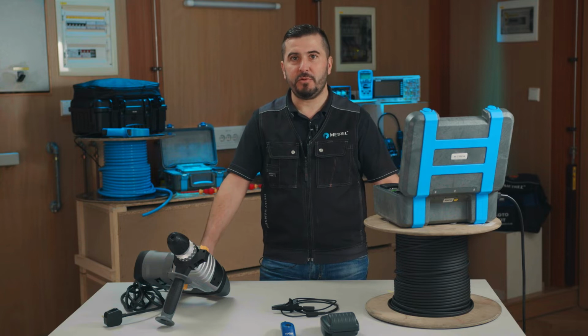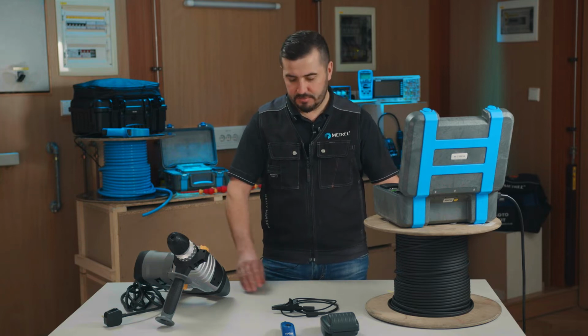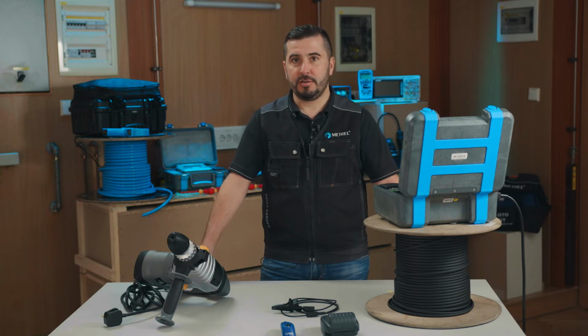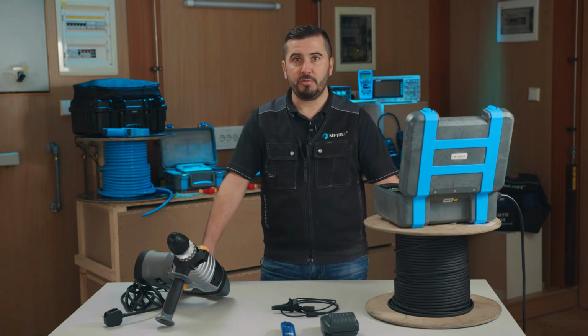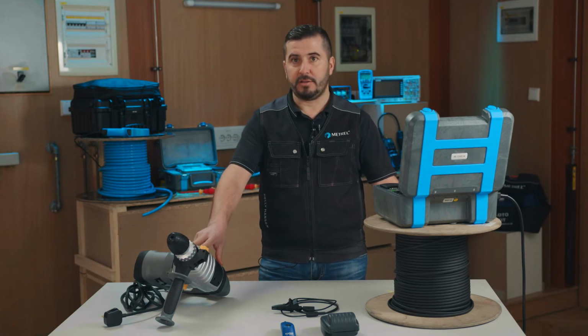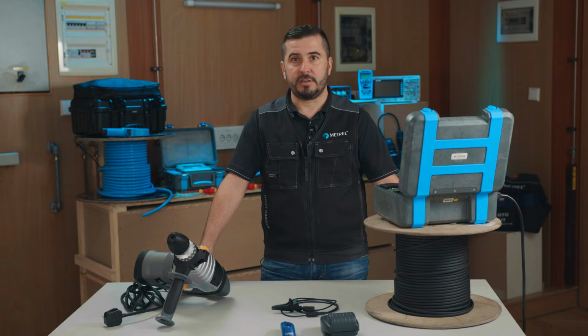So instead of it, we will perform the following tests: insulation resistance test with a probe and touch leakage test, for which the probe is also applicable. For both tests, it is crucial that they are performed with the appliance main switch in the on position. It is also important that the probe is connected to the accessible metal part. If not, then the electrical tests are invalid and the potentially problematic or dangerous voltage or current that could appear on the metal part will not be recognized by the instrument. Each examination of electrical equipment must consist of a thorough visual inspection, which is in some cases even the only applicable test option.